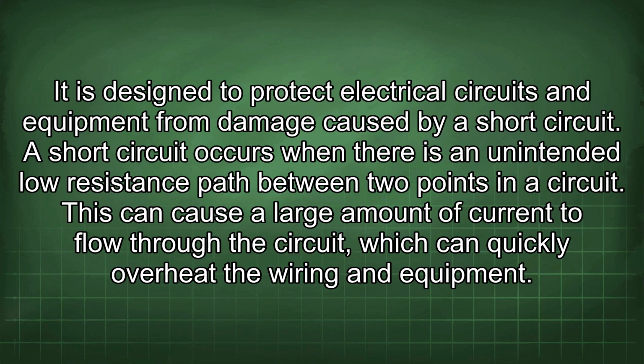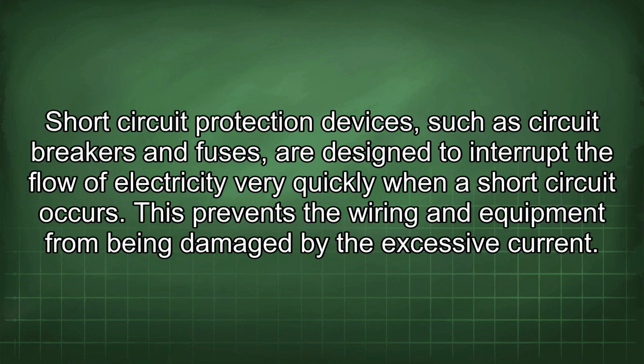A short circuit occurs when there is an unintended low resistance path between 2 points in a circuit. This can cause a large amount of current to flow through the circuit, which can quickly overheat the wiring and equipment. Short circuit protection devices, such as circuit breakers and fuses, are designed to interrupt the flow of electricity very quickly when a short circuit occurs. This prevents the wiring and equipment from being damaged by the excessive current.